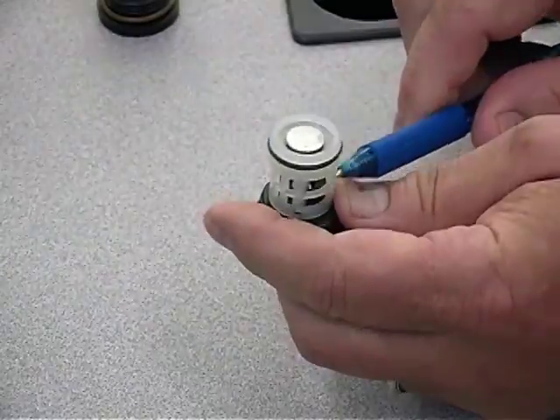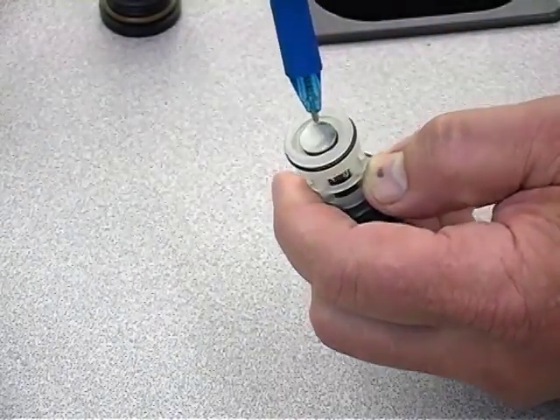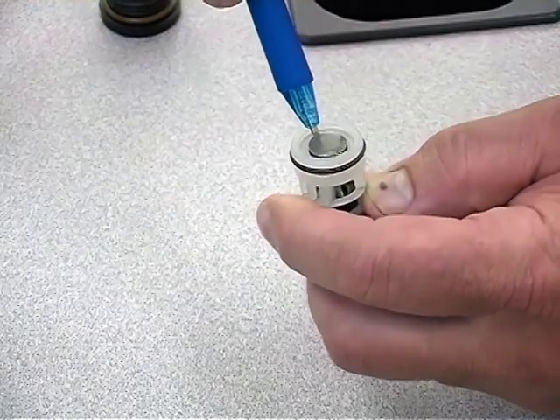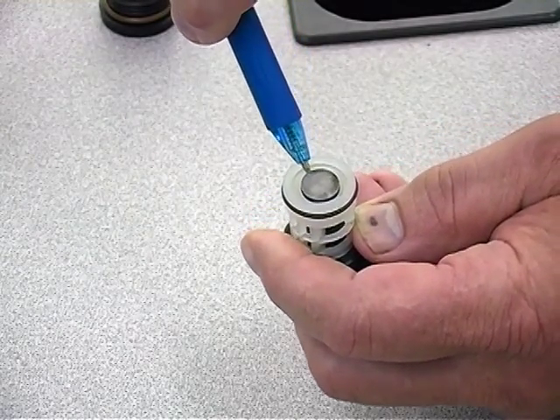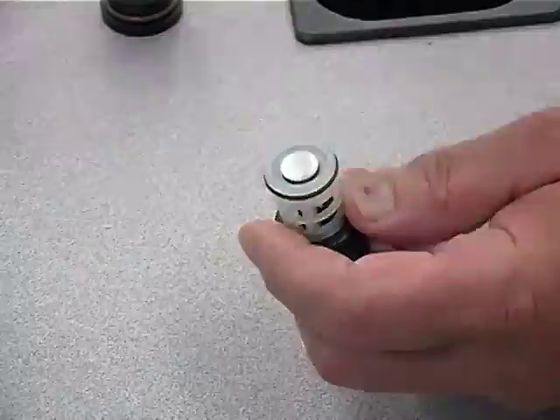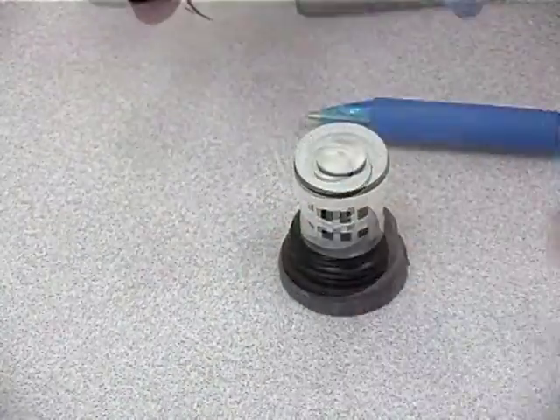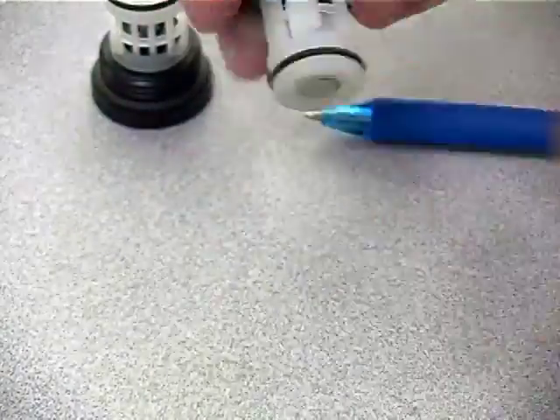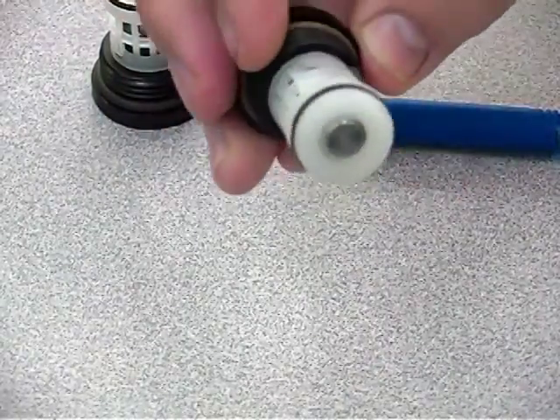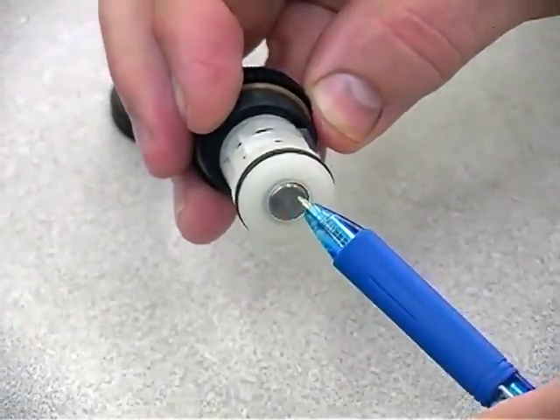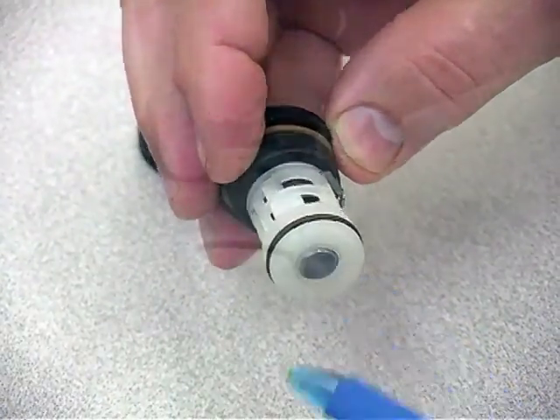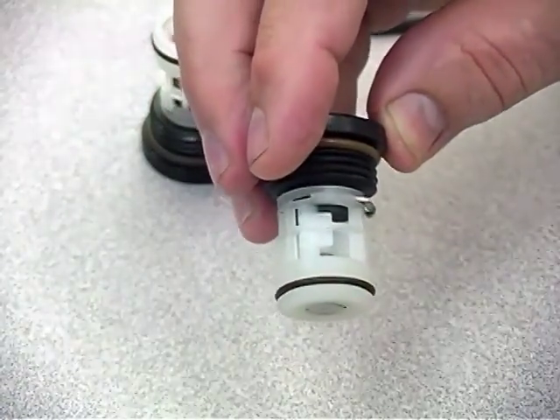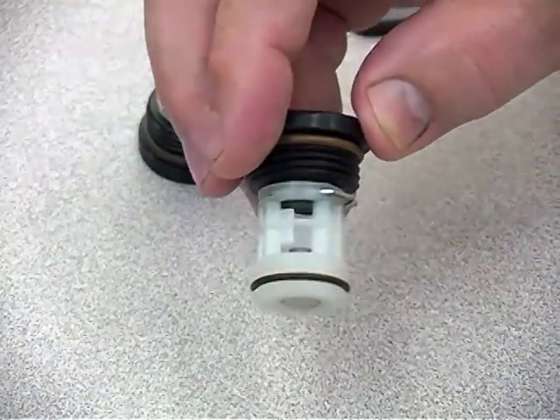Chemical comes through the valve body to prise up the poppet around the seal. The chemical comes out and goes up through the pump, as we've seen before. When the piston pushes over, it forces the chemical up through the discharge valve, and the discharge valve basically is sitting upside down like this. Chemical going through pushes the little poppet in by the seal, goes up through the valve body, out the chamber, and out to the discharge line.